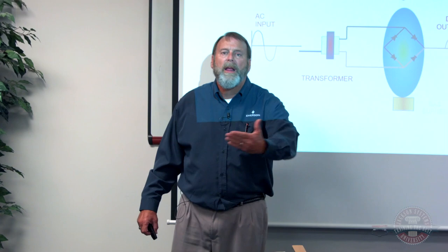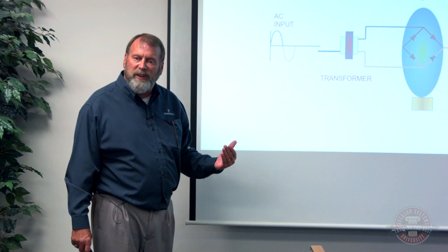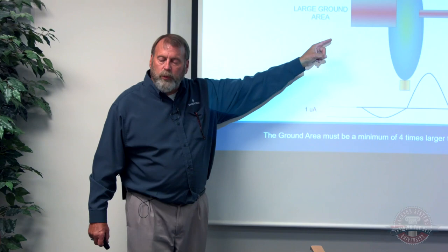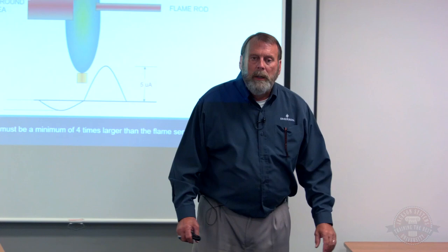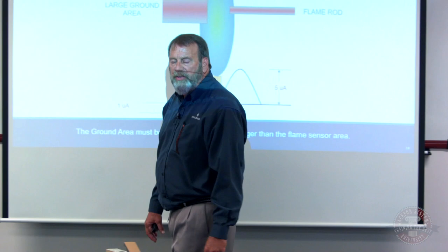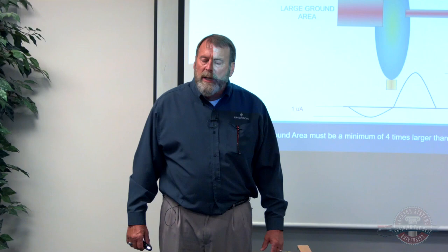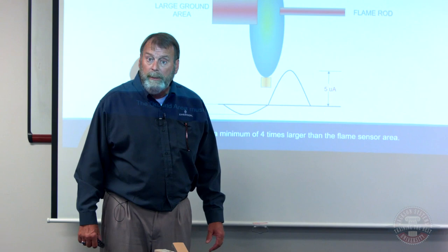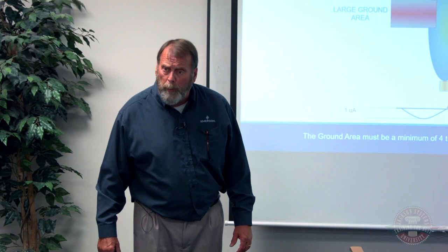Now, why do we want to understand this? I took about 10 minutes of your life, you'll never get back, to talk to you about ground, because that's really what the issue is. The majority of times, it could be the probe, but I've run into so many calls on our tech services, because the tech services group works for me. Guys, we get 400 or 500 phone calls. I dread this time of year because I'll get 400 or 500 phone calls in a day from contractors all over North America. And in the first 6 weeks of winter, the majority of the questions are flame rectification. And it comes down to, oftentimes, it's the ground and not the probe.